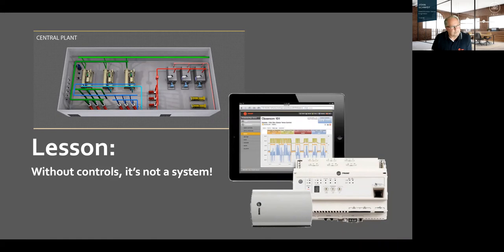A rule of thumb is you can get 3/4 of the flow with half the energy, half the horsepower of the pump. That just follows the pump curve. So if we can slow that flow down just by 1/4 or 25%, we're going to save half of the energy of that usually very large pump or group of pumps.